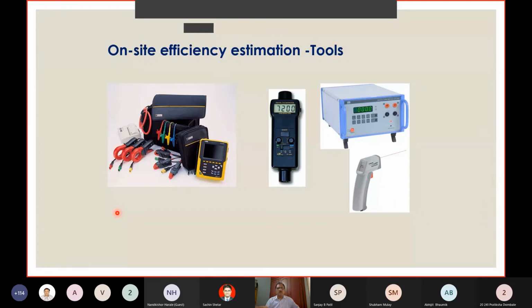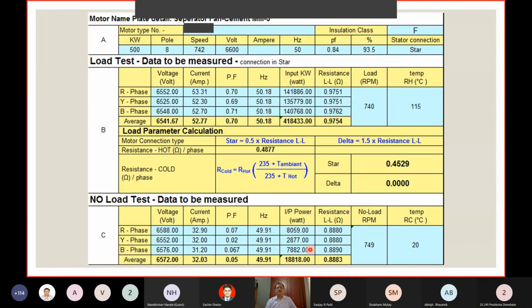Some of the tools which we use for on-site efficiency estimation are a power analyzer, a stroboscope, a tachometer, and a non-contact thermometer. We also use a thermography camera nowadays, with which we do an analysis and explain to the customer what they can do with the system. I have a couple of slides on what on-site efficiency estimation really does. In my over enthusiasm, I have taken a 500 kilowatt motor here, which is an HT motor, 6.6 kV, where we have made measurements on load and no load.